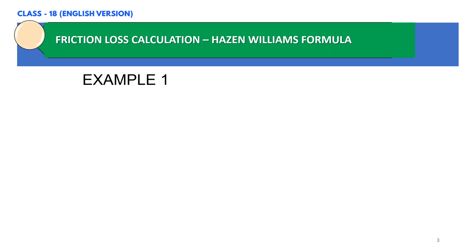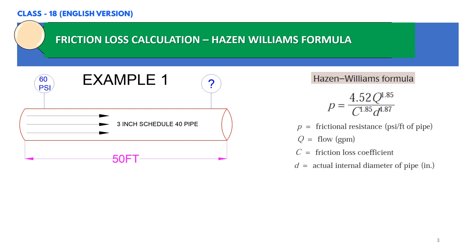Here we have the Hazen-Williams formula: P equals 4.52 times Q to the power 1.85, divided by C to the power 1.85 times D to the power 4.87. This is the standard formula used to calculate friction losses. P represents frictional resistance in PSI per feet of pipe, Q represents flow in gallons per minute, C is the friction loss coefficient, and D is the actual internal diameter of the pipe in inches, which can be found from the manufacturer's data sheet.